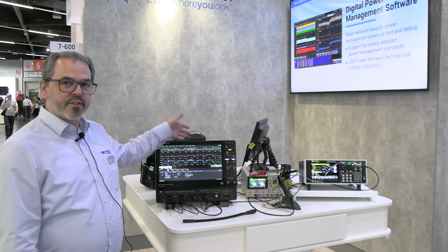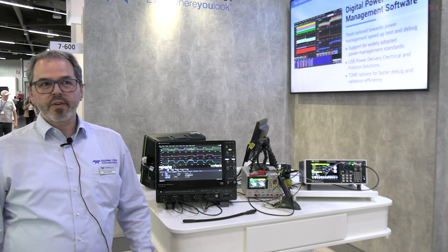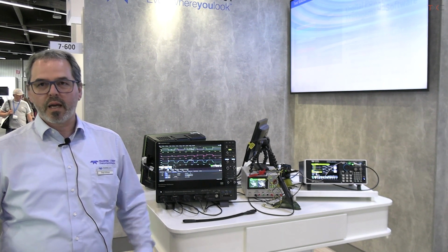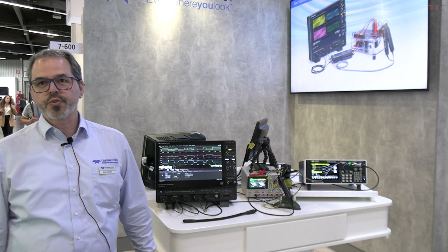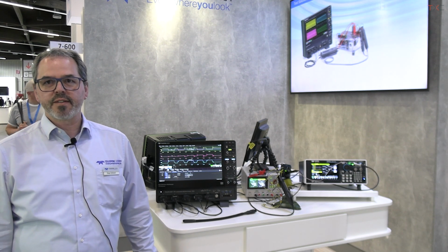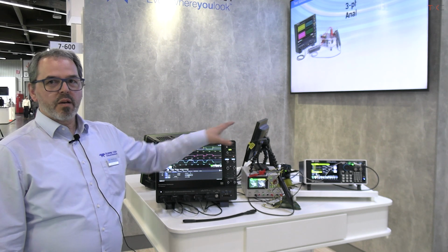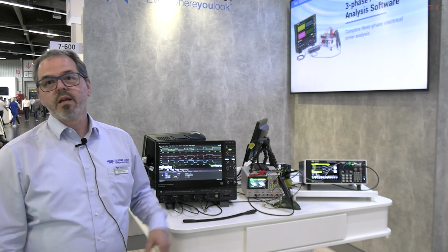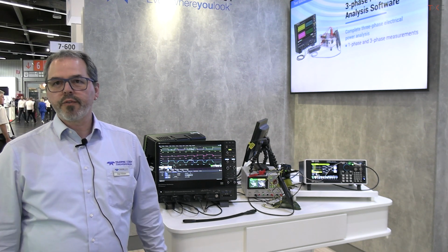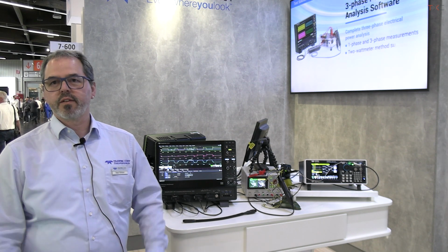I'm Field Applications Engineer at Teledyne LeCroy, and I'm here today at the PCIM exhibition in Nuremberg, and I want to show you our double pulse testing setup. We have an instrument, our WavePro HD, that goes up to 8 GHz of bandwidth, and we have up to 5 gigapoints of memory, and we have real 12-bit vertical resolution, so we have really 12-bit ADCs inside the scope. Besides that, we have a signal generator, the T3AWG, and with that generator we can create the double pulse waveforms to control the switching devices.